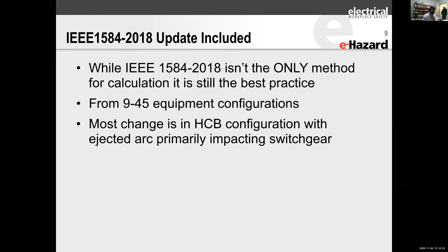When the standard was published back in 2002, the idea was, let's get something that can help folks, okay? And within that time, there was limited budget, limited understanding, limited equipment availability. And so what they did back in 1584, 2002, was they provided us a guideline via an IEEE standard, which was the best that we had at the time. But over the years, they realized, folks, we need to do a little bit more. We need to test a little bit more. And you can see that the equipment configurations that they looked at previously actually jumped up from 9 on the previous standard up to 45 changes.